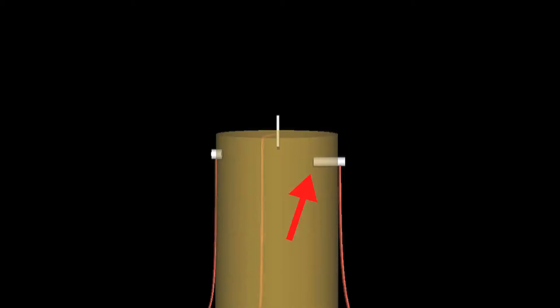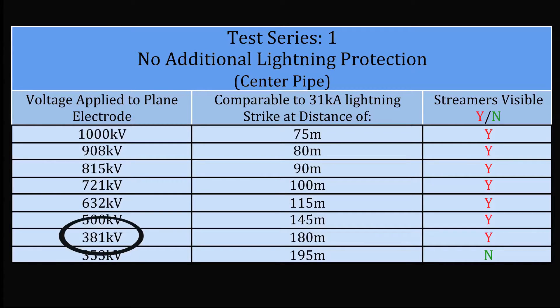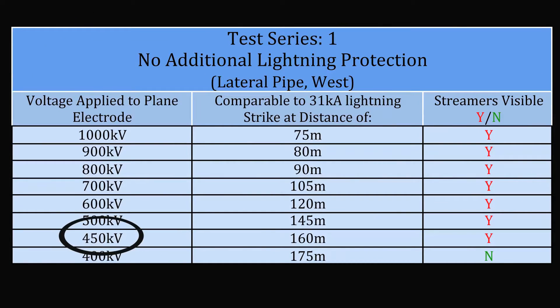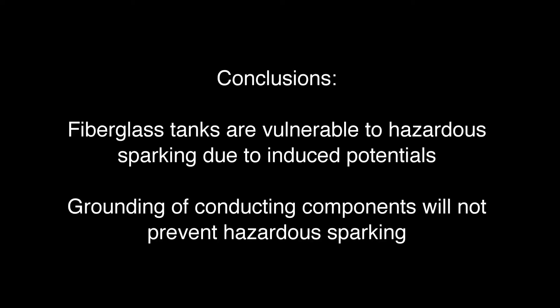The same sequence of tests was conducted on the two laterally inserted pipes with roughly the same results. Sparking continued down to an applied voltage of between 381 and 450 kilovolts. The following conclusions can be drawn from this first test series.